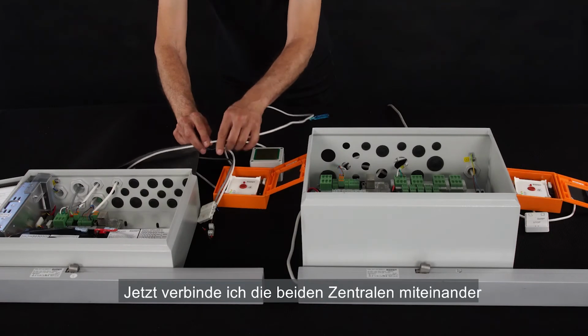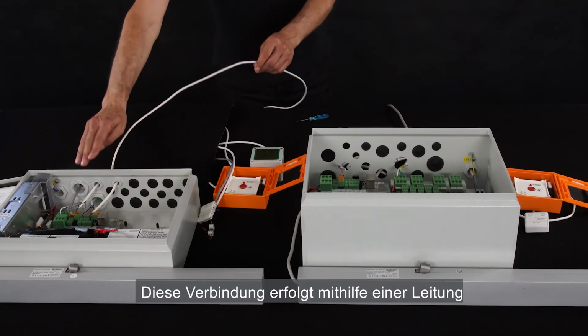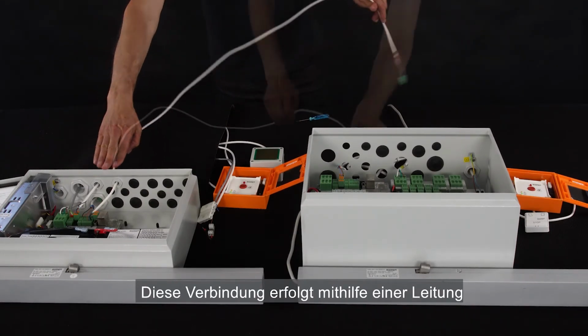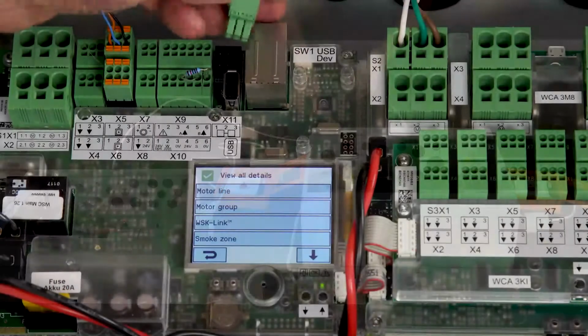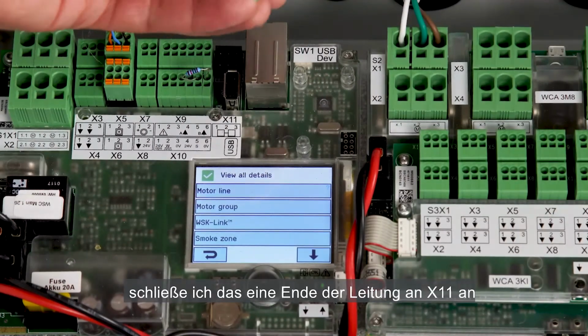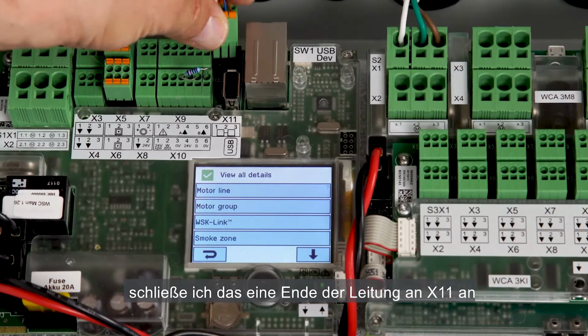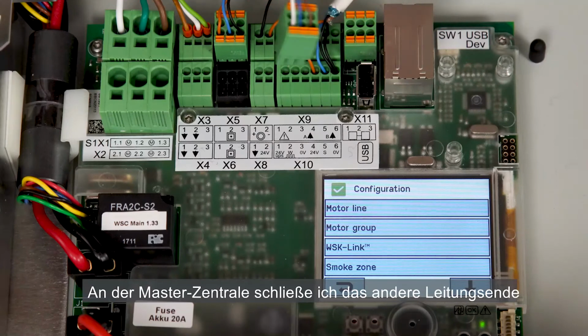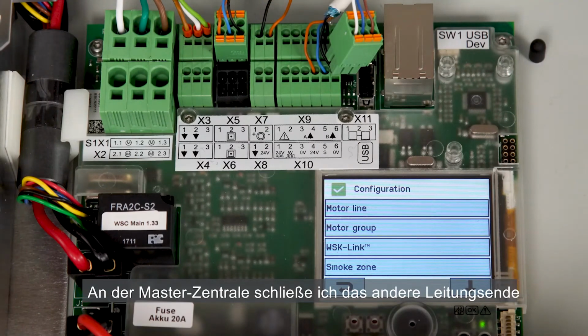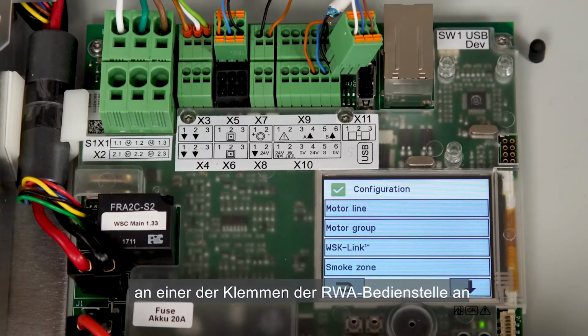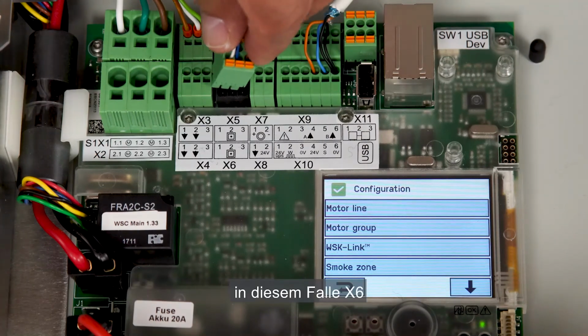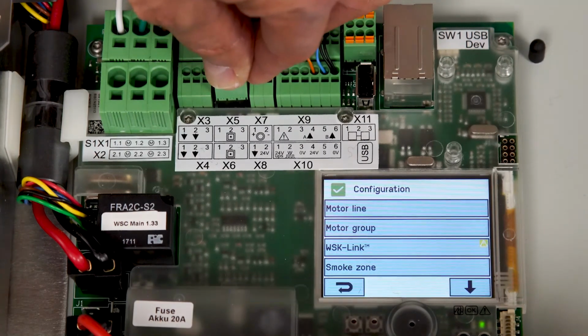I'll now connect the two panels together. I have a cable that I use to make the connection. On the slave panel, I'm connecting one end of the cable on input X11. On the master, I'm connecting the other end of the master-slave cable on one of the break glass unit terminals, in this case X6.